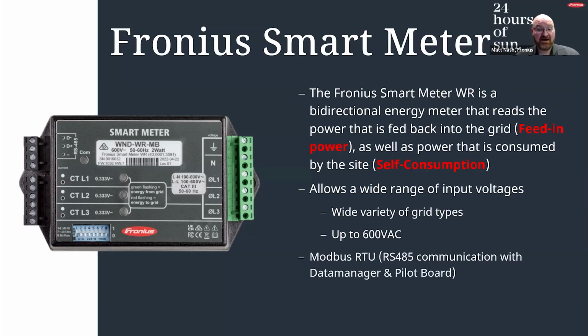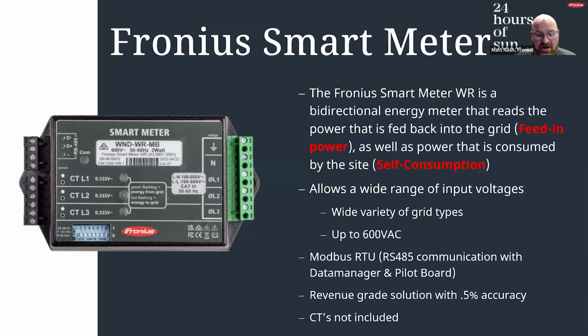It communicates via Modbus RTU with the RS485 connection, either on the data manager for our older models or the pilot board for the Gen24. It is a revenue grade solution with 0.5% accuracy. One thing to note is the CTs are not included. We do recommend utilizing the Continental Control CTs. They are the manufacturers of our smart meters, so they're the most compatible.